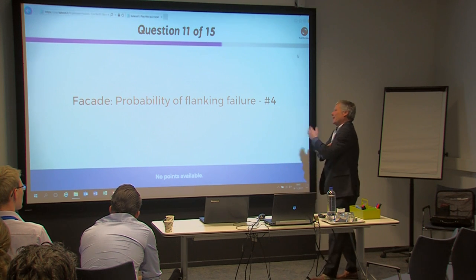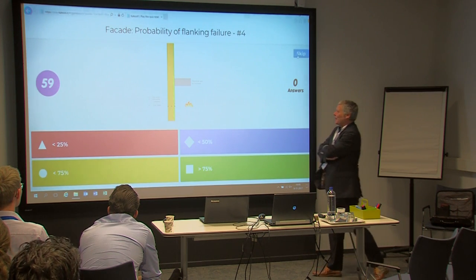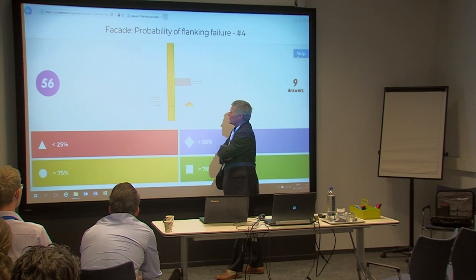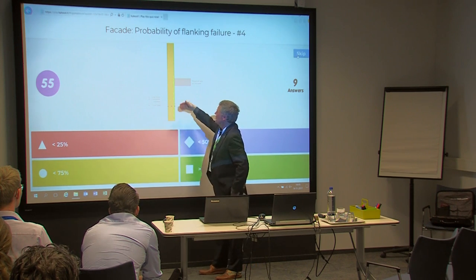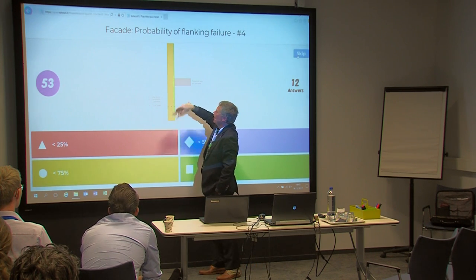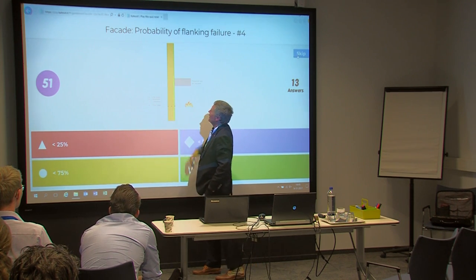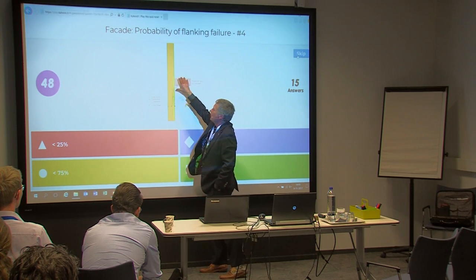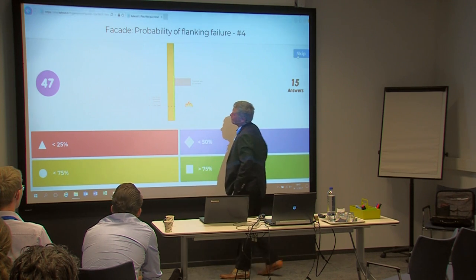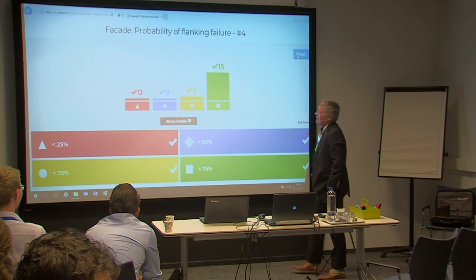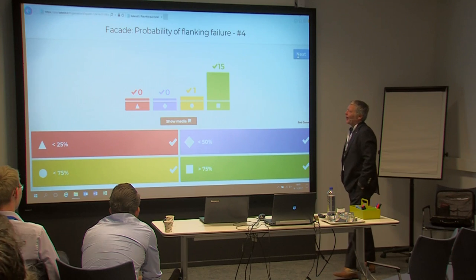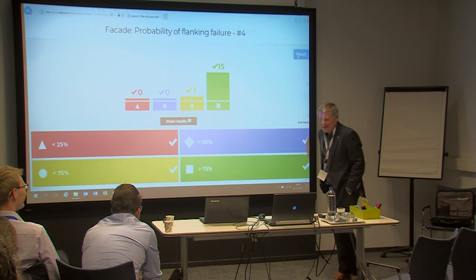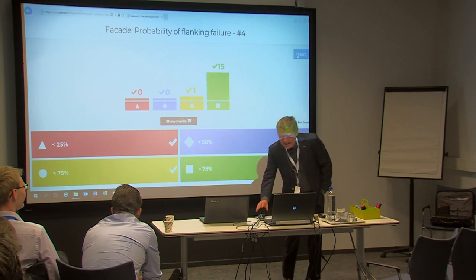The fourth facade detail is the same as the previous but with combustible insulation material — steel cladding with combustible insulation going along the compartment wall. The group agrees easily: a high failure probability is expected.